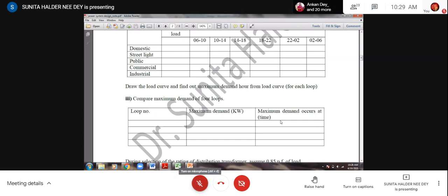And so here you will get the same. Maximum demand will obviously not be the same, because in each sub-block the loads are not uniform. They are near to each other but not the same throughout the four sub-blocks. But whether the maximum demand is coming in the same time span or not, you check it. If it is not, then you interchange some data nearby.